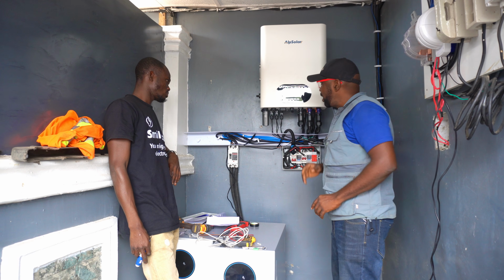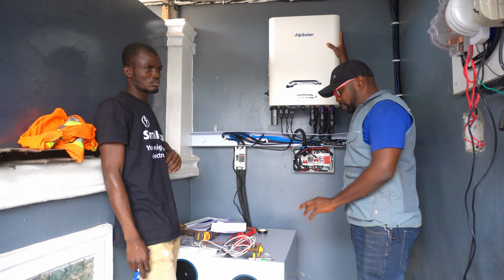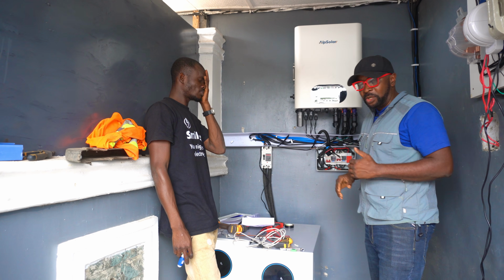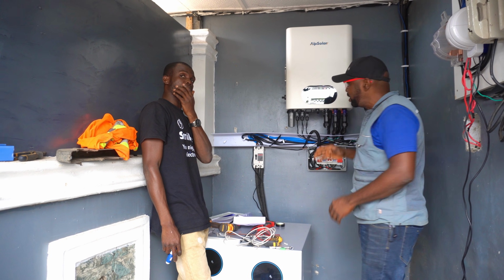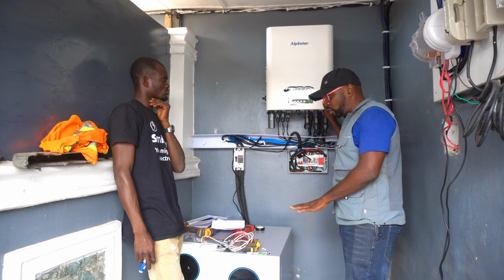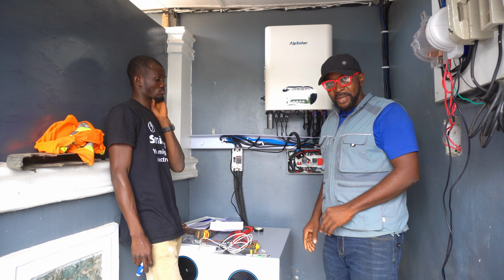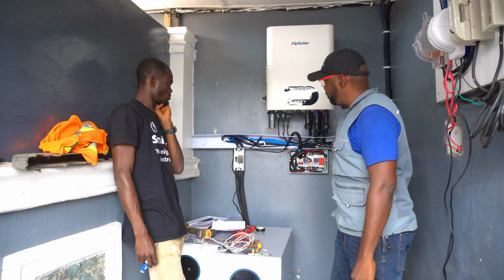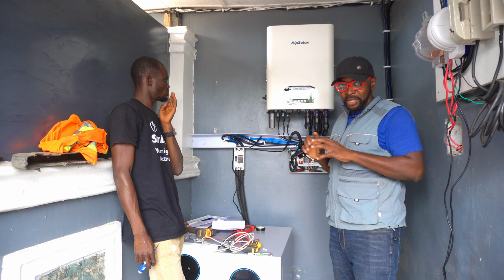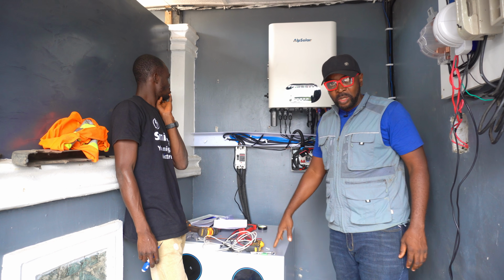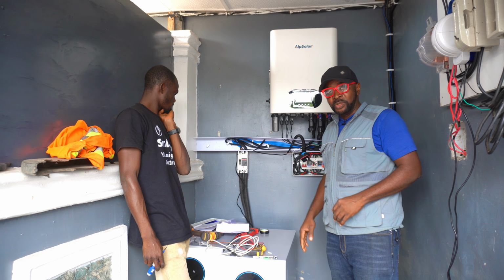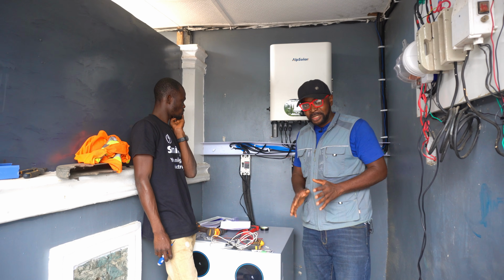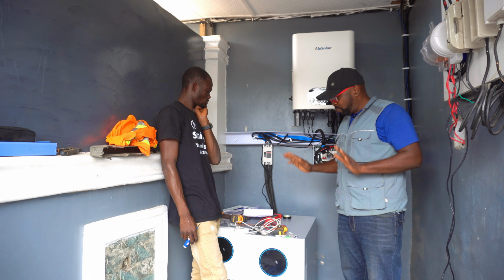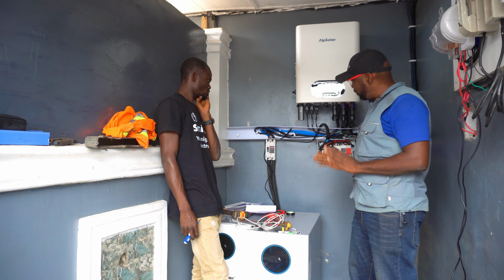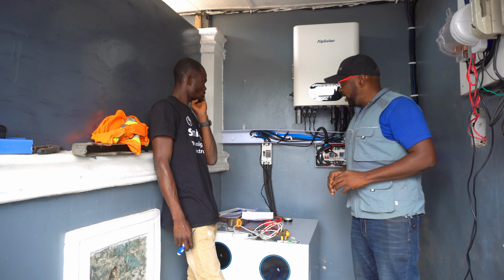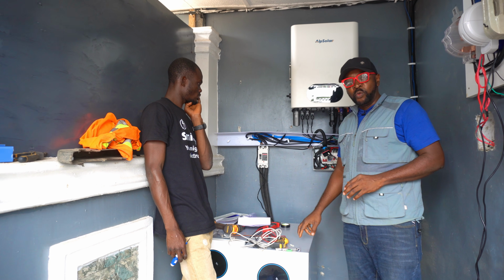At this stage, we want to connect the inverter to communicate with the batteries. It's very important that when you do your installations, the battery has to be connected to the inverter, so the inverter can monitor what's going on in the battery, because there's a BMS built into the battery and also a BMS on the inverter. These communicate and share information, so the inverter knows when the battery is fully charged and other information, ensuring the batteries charge and discharge at the same current, monitoring temperature and everything. So it's very essential and vital that this communicates with the inverter.